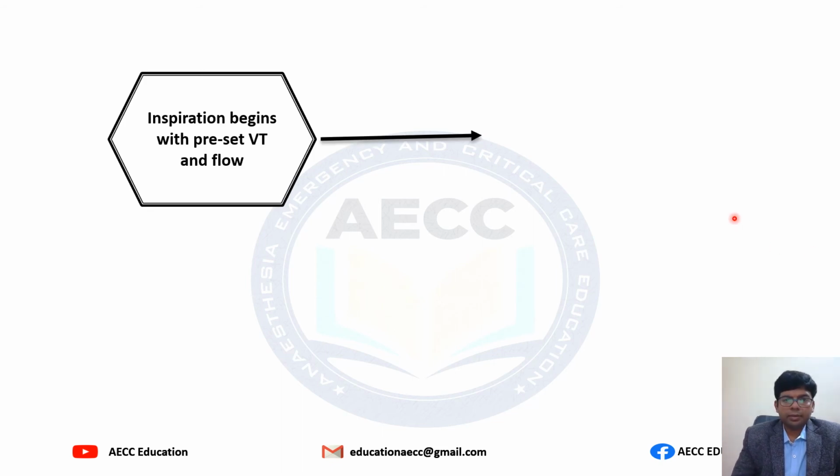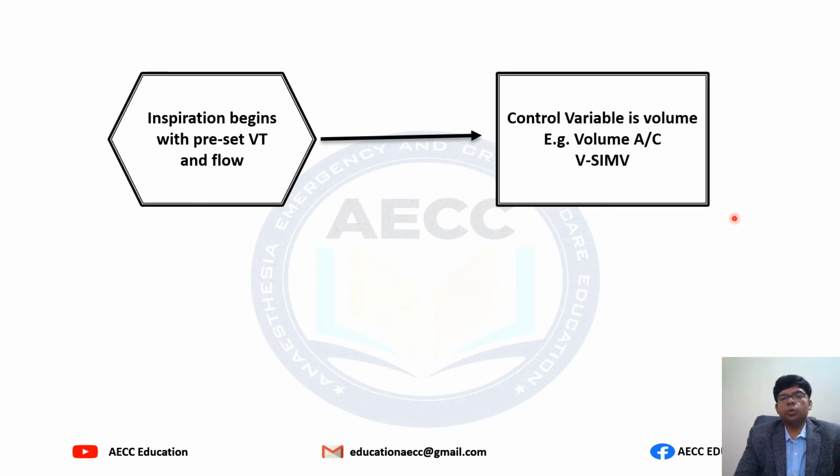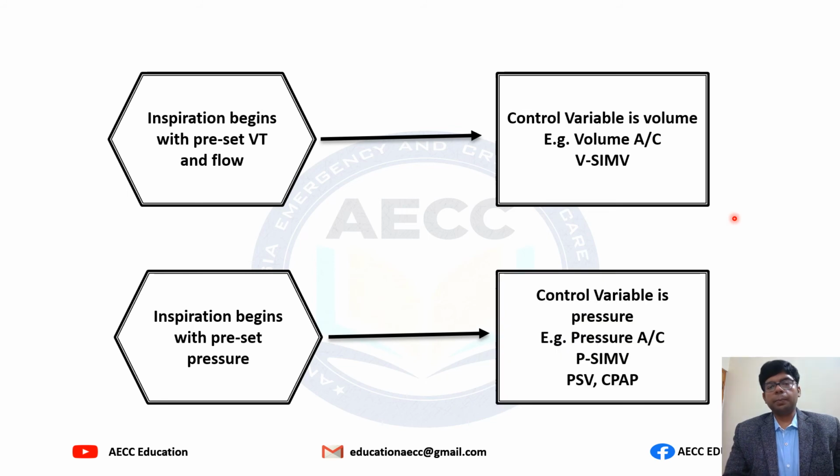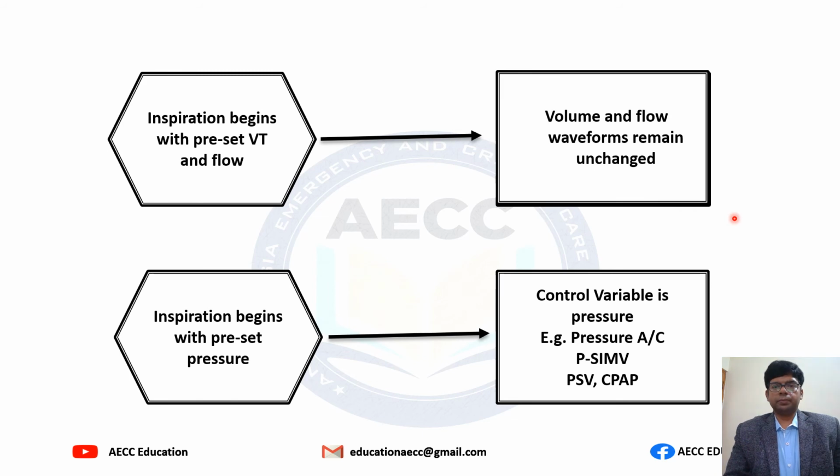In case of the volume control, inspiration begins with the preset tidal volume and flow. So the control variable here is the volume. Examples are volume assist control and volume SIMV. If the inspiration begins with the preset pressure, then the control variable is the pressure. Examples: pressure assist control, pressure SIMV, pressure support ventilation and CPAP.